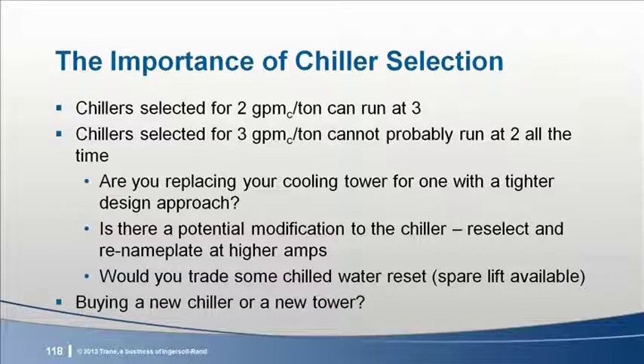And then, suppose you have to decide between new chillers and new towers, at least for right now. You can probably get the lift capability that you need for reducing condenser flow rates in either component, unless your chillers are really old or have little extra lift available. The important thing to realize is that for an existing tower, when you send it warmer water, it comes back colder. The effectiveness improves when the initial temperature difference is higher. The only way to hold tons constant is to lower the flow rate.